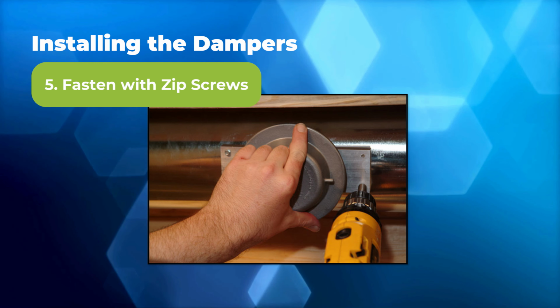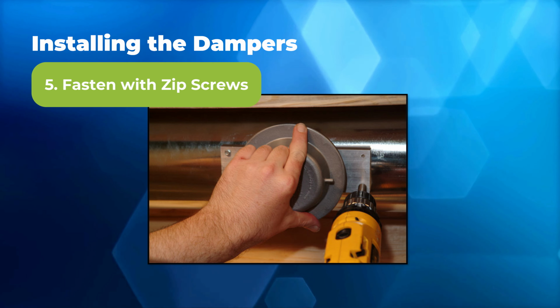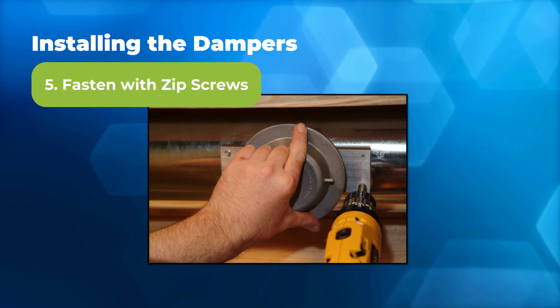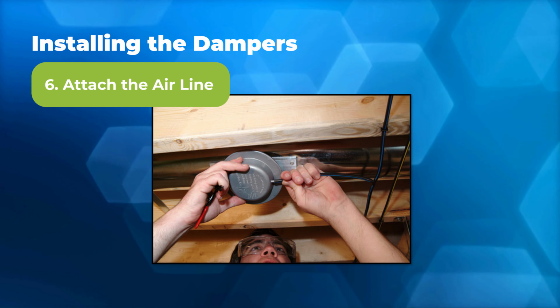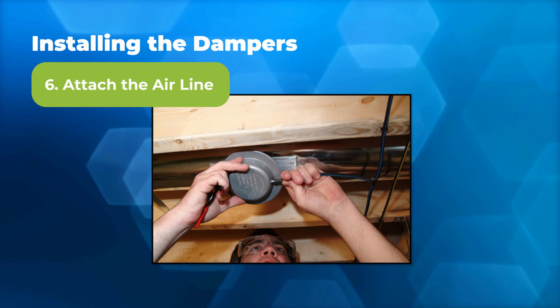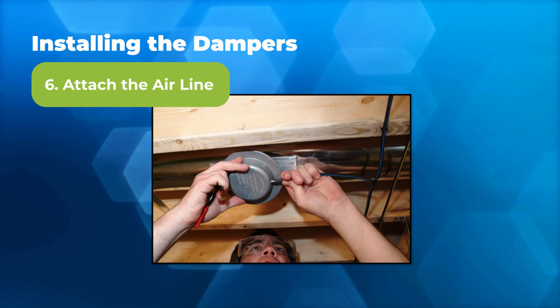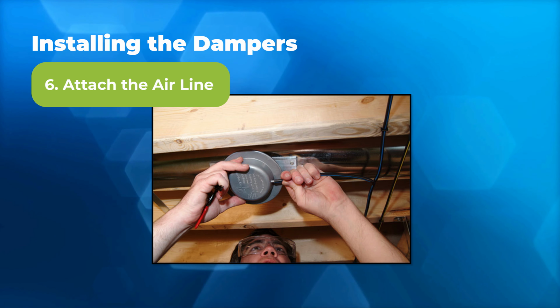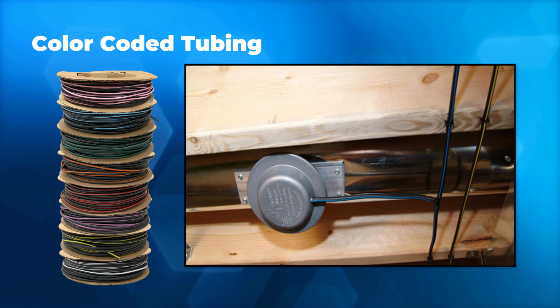Once you get the damper turned in place, you're just going to put 4 1.25 inch zip screws in, and then you're going to attach the air line to the tubing. So the air line is going to come in 8 different colors. If you guys don't know, the biggest panel that we offer is an 8-zone Air Boss panel, so you can do each individual damper zone with its own color.